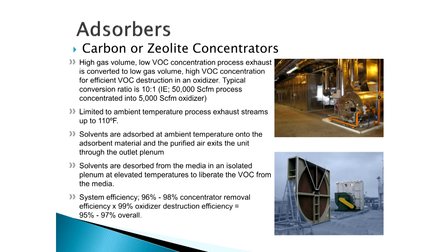We actually create a situation where we can make the oxidizer self-sustain, and then we take the heat off of the oxidizer and we actually use that to regenerate the carbon or the zeolite that's in the rotor or the disc. And so what you see down here at the bottom is that the vast majority of this zeolite rotor is in the incoming gas stream and it's adsorbing solvents.